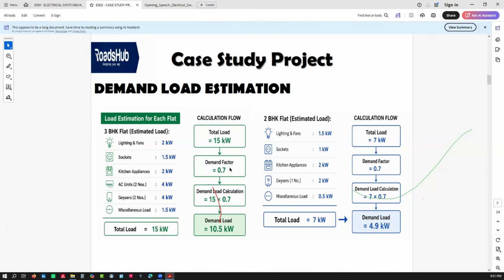So for the 3 bedrooms, we have a demand load of 10.5. For the 2 bedroom, we have 4.9. I want to give you a secret: for people who do building management services, anytime you get a value of 10.5 kilowatt, compare it to 7. Is it greater than 7 or less than 7? If it's greater than 7, then you can use a 3-phase DB on that system.